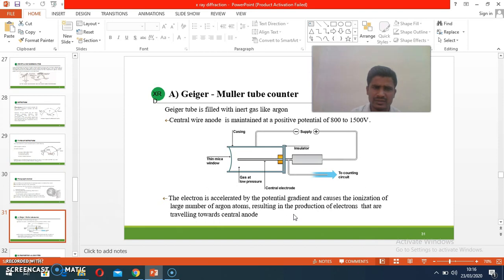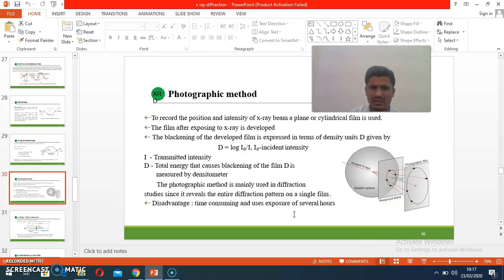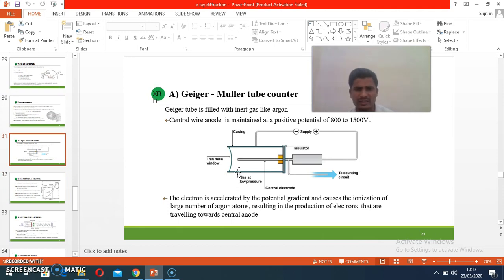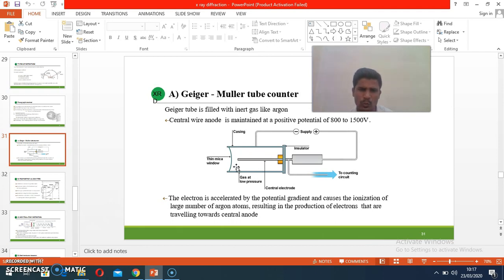The Geiger-Müller counter method: the Geiger-Müller tube is filled with argon gas. Through the tube there is a small window made of mica. X-rays pass through this mica window and interact with the argon gas, causing ionization of the gas. When ionization takes place, electrons are produced and go to the central anode. The tube's cathode and anode are maintained at a potential of 800 to 1500 volts.